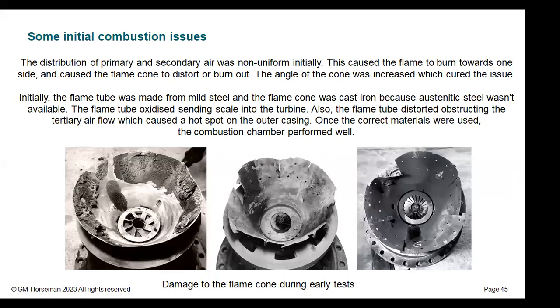Okay. So we've really described the development of the machine up to that point. I could stop, but there were some other interesting, historically important things, and I'm going to show them now. It's not a huge number of slides, but you might be interested. Some of these were operational issues. When the machine was very first run, we didn't have the delivery of the austenitic materials. So we made the flame cone out of cast iron and the body of the combustion chamber out of either carbon steel or carbon half moly. Unsurprisingly, the flame cone distorted, but it performed well once we had the right material.